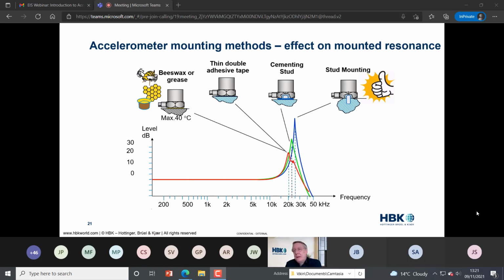The ideal method of mounting is to drill and tap the surface, use a metal stud and then screw the accelerometer down onto that stud. And to improve the high frequency even further, you can put a small amount of silicone grease underneath the accelerometer to take up any voids. So that is the resonance that you would see shown here in blue, where you've got a perfect mount.